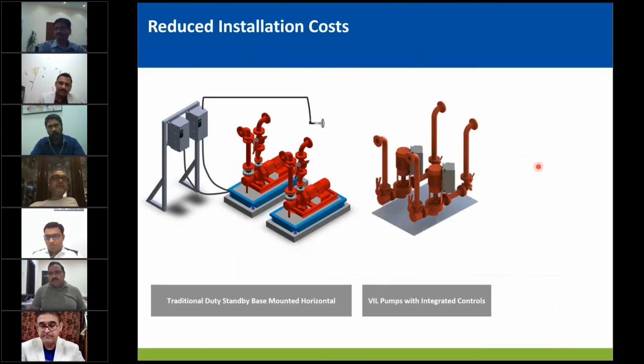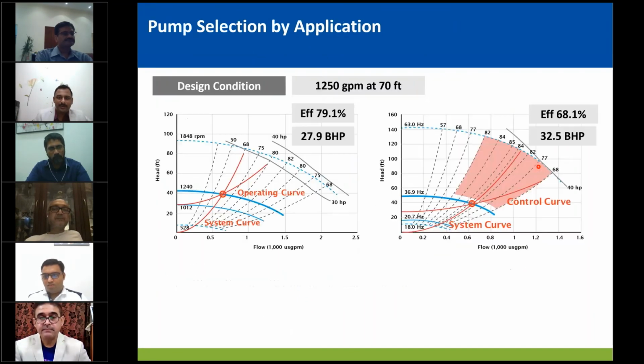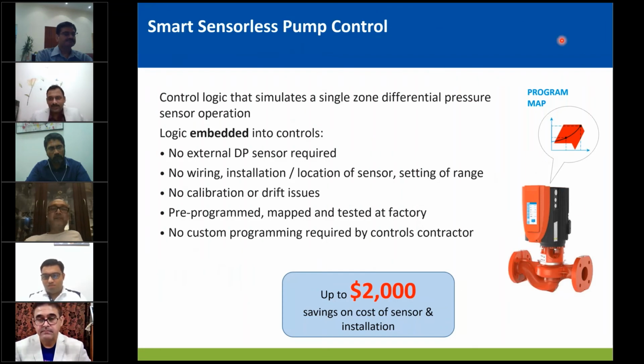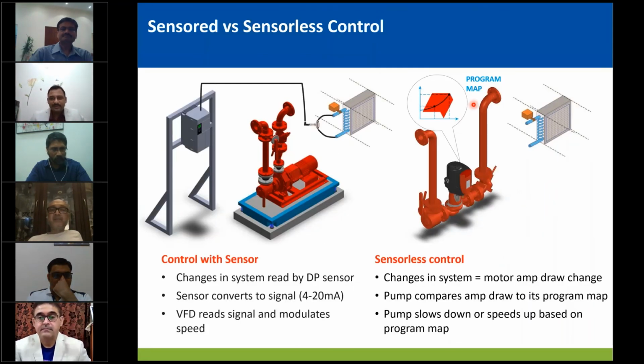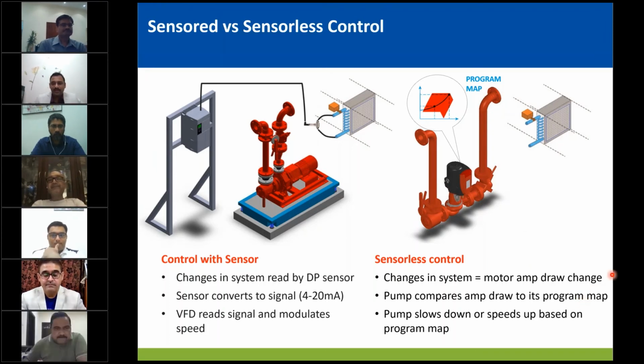Okay, so the smart pumps today have the performance map of the pump embedded in the controller itself. So the performance maps are in the pump, so it knows where it is operating, number one. Number two, it's a closed loop circuit, and any pressure change or flow change in the system, according to the simple affinity law of a pump, should change the amperage of the pump. Now, if the system conditions are changing, either the flow or head or both, then amperage is changing, and by sensing that amperage change and looking at the performance map, the smart pumps can sense the demand of the building, and as per the demand, they can slow down. So when we say no sensor or sensorless, the inbuilt sensors are made use of with the program maps and intelligence built in.